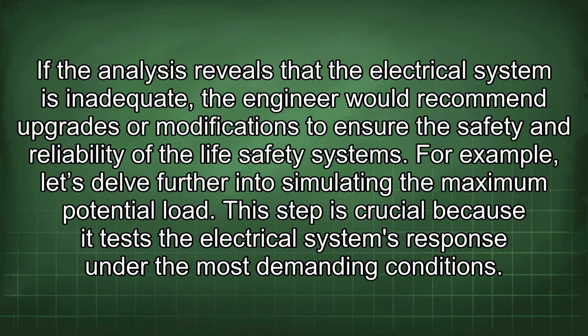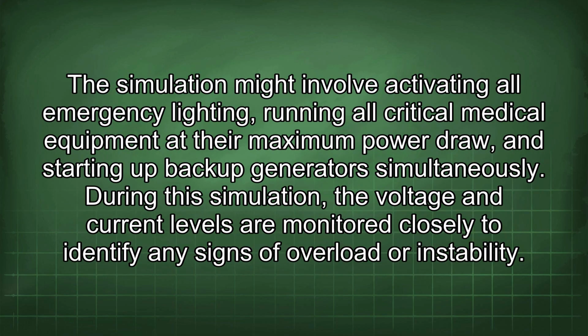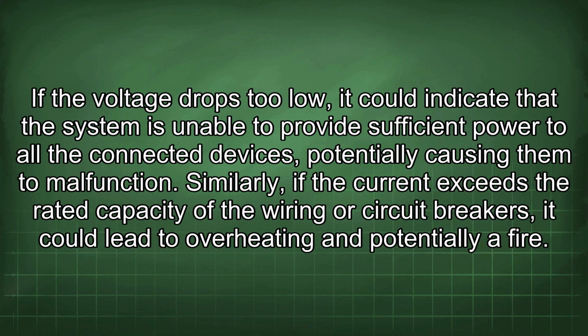For example, let's delve further into simulating the maximum potential load. This step is crucial because it tests the electrical system's response under the most demanding conditions. The simulation might involve activating all emergency lighting, running all critical medical equipment at the maximum power draw, and starting up backup generators simultaneously. During this simulation, the voltage and current levels are monitored closely to identify any signs of overload or instability. If the voltage drops too low, it could indicate that the system is unable to provide sufficient power to all the connected devices, potentially causing them to malfunction.